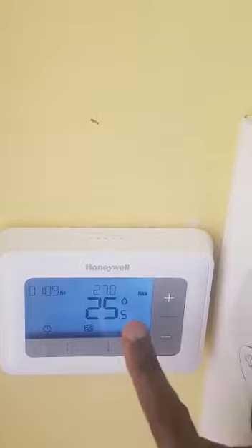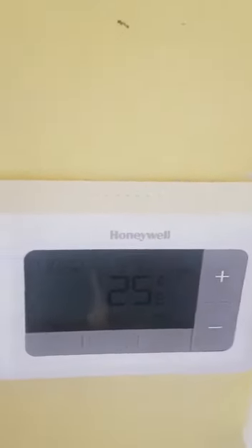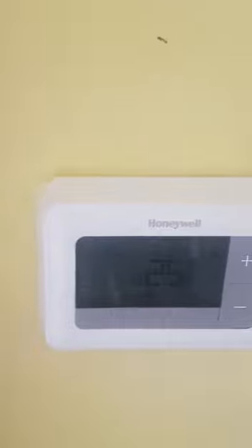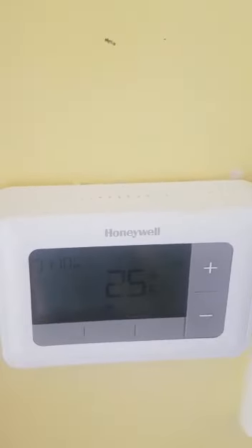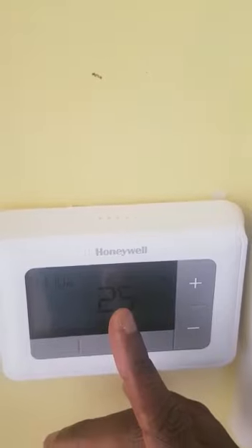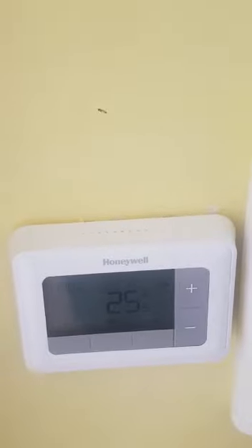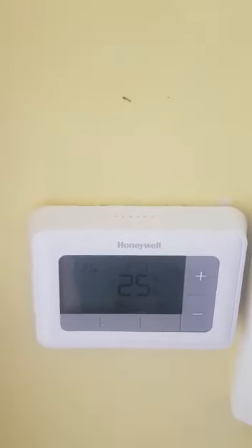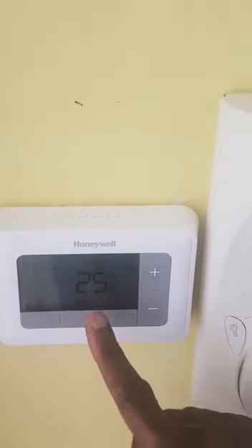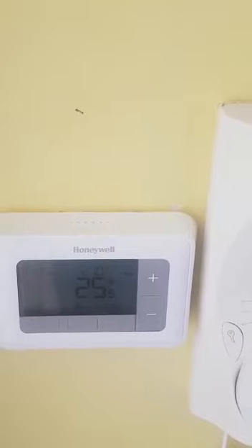I'm gonna leave it. You will see a flame icon which tells you that the boiler's come on now. If you check the boiler and you listen, you will hear that the boiler is heating up. Right. So now the heating is on, and it will get to 27 and stay there. It's important to remember if the temperature you want is less than 25, it's not going to work. It will not come on. The temperature that you set has to be above the current room temperature, which is the big figure, which we can see there is 25.5 degrees.